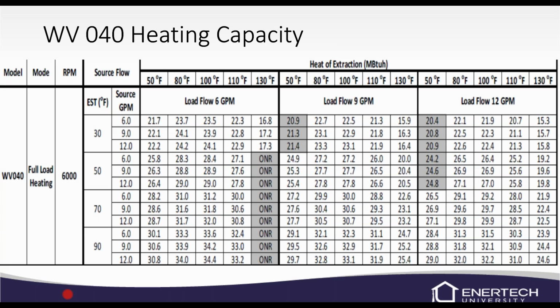With that said, if we have a 5 ton unit, you don't want to put 5 tons of radiant in the floor and then have a 5 ton air handler for doing heating as well. The unit will never shut off. It'll always be switching back and forth. It'll be hard on the unit. So it's a 5 ton unit, so it can only do 5 tons, whether that's 5 tons of radiant, 5 tons of forced air, or 5 tons of the combined. It's the total load. So we just don't want you to try to do too much with this unit.